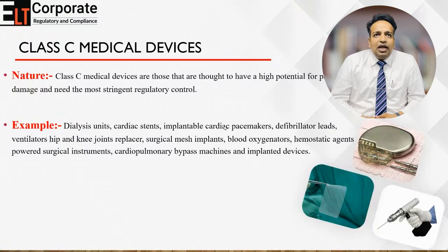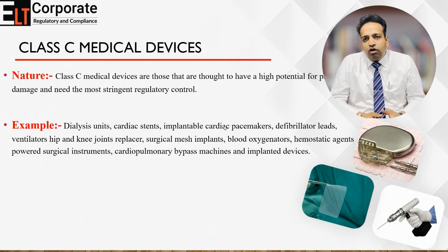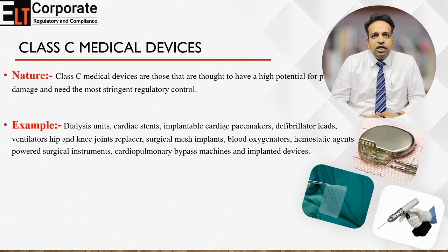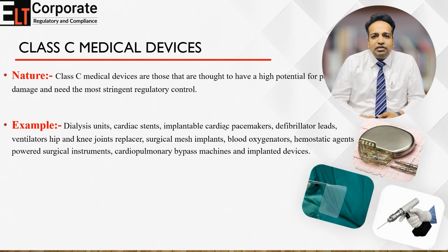Class C devices are the riskier equipment. For Class C equipment there is a stringent regulatory environment, with stringent requirements for clean rooms and other environmental conditions for manufacturing such devices. Classic examples of Class C can be items related to respiratory functions — such as oxygen and blood oxygen generators — bypass machines, implanted devices, powered surgical instruments, orthopedic equipment, cardiac stents, etc.